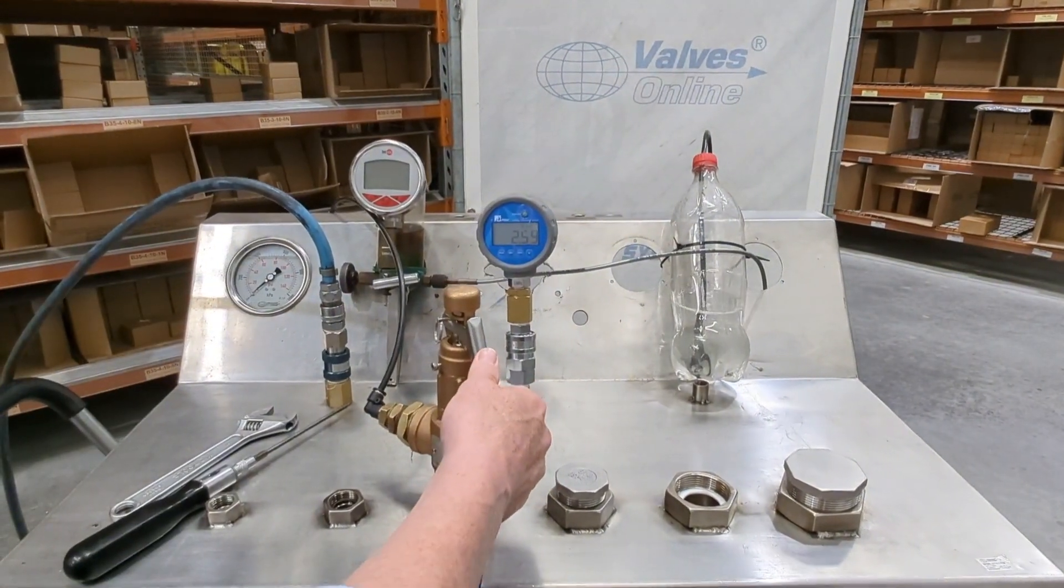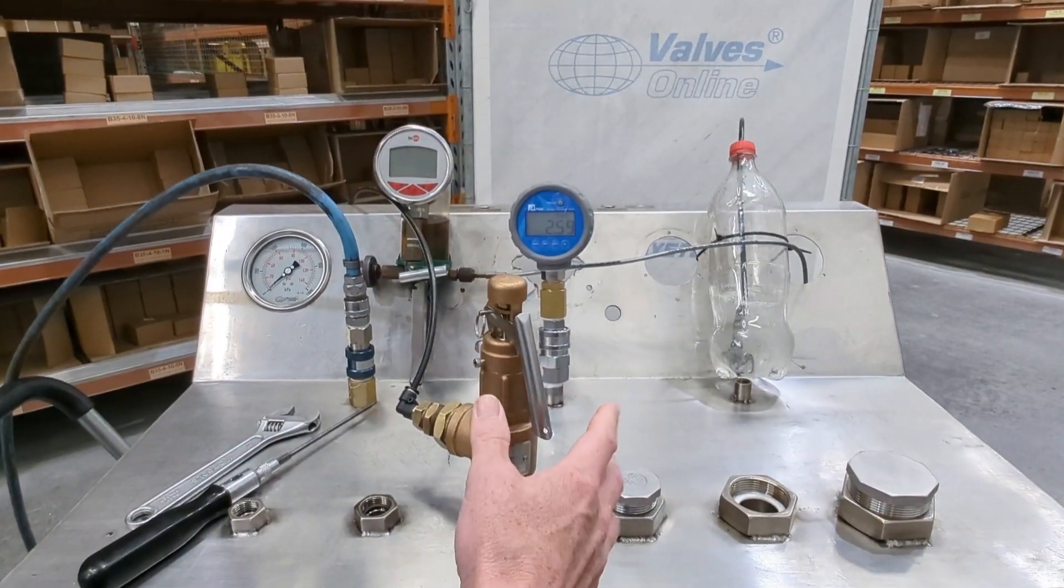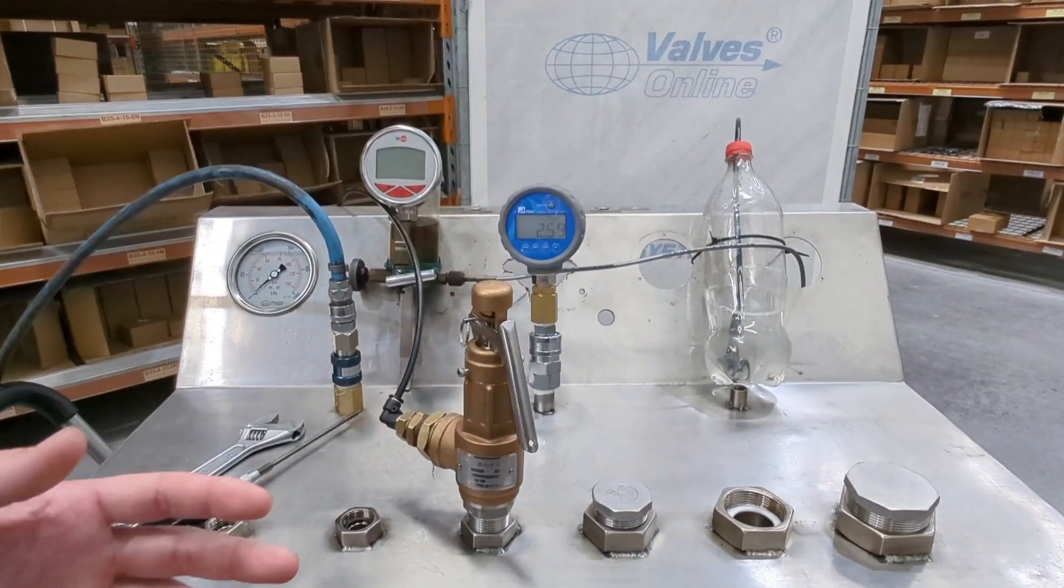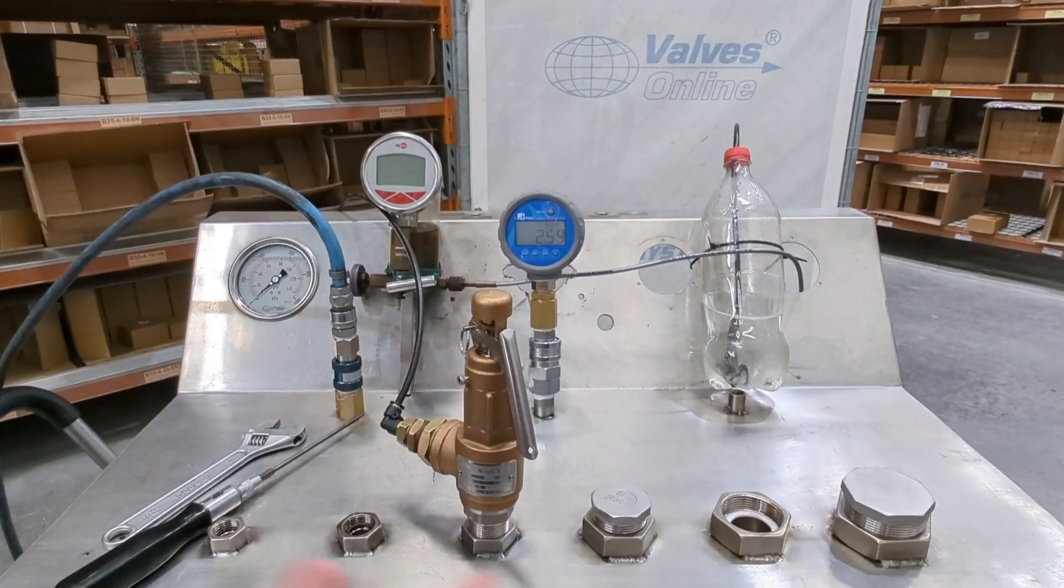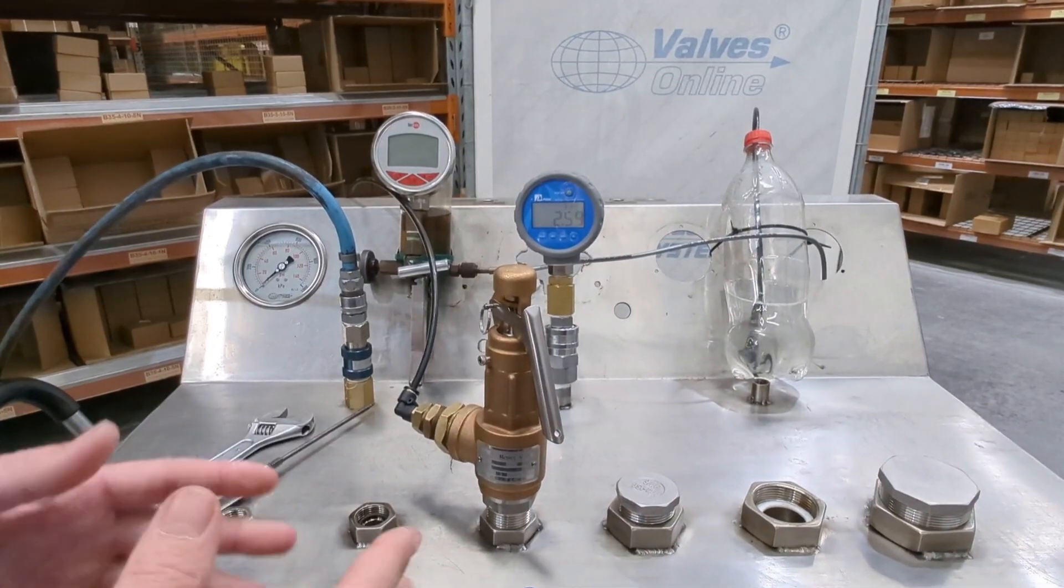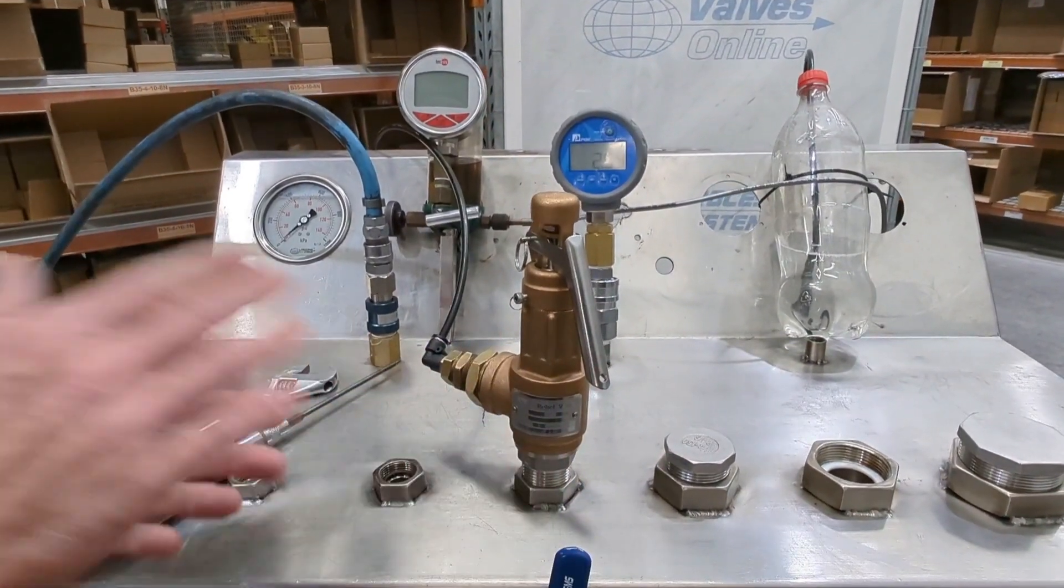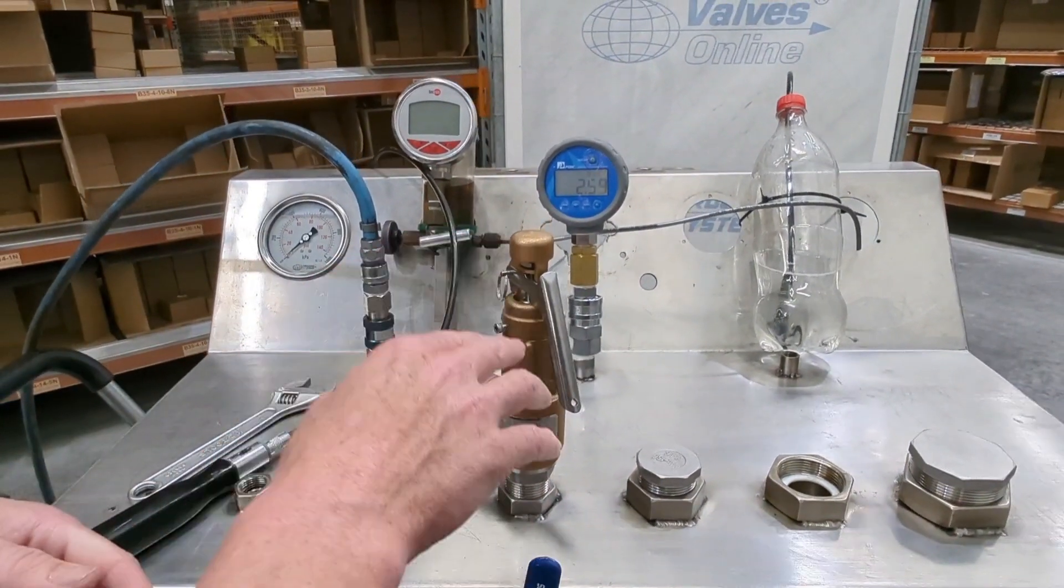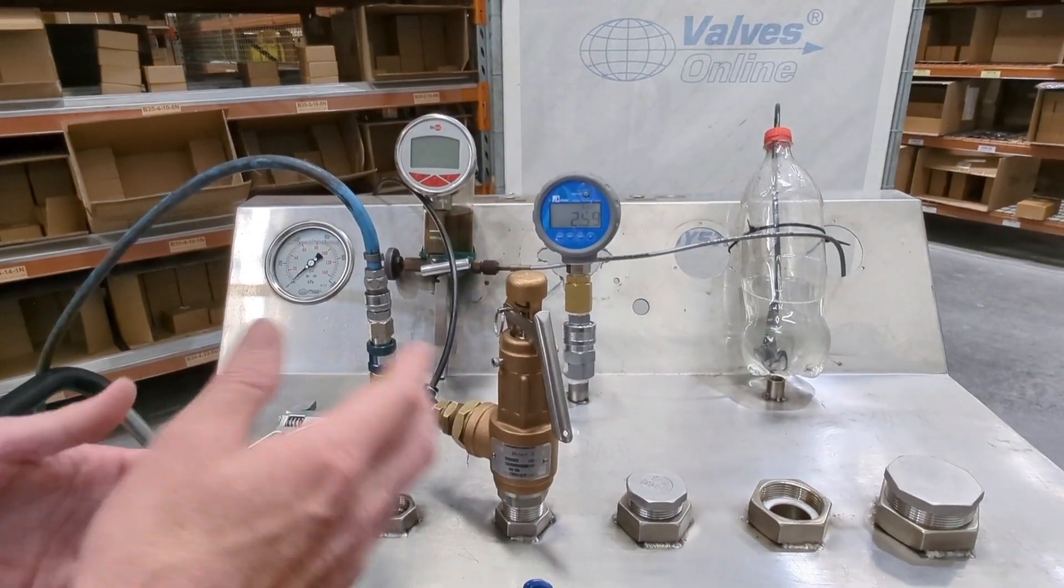Now when you buy this, it may not be set if you haven't required setting or you have ordered a setting. The spring range has a pressure range—for instance, this one is 2 to 5 bar. Within the spring range, what that means is this can be set at its relief point anywhere between 2 and 5 bar. So what you need to do is set it.